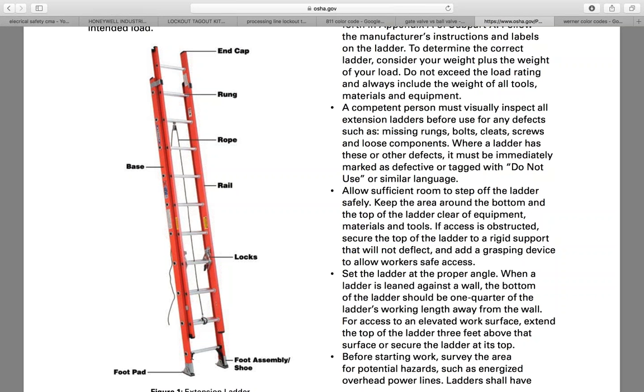Looking at page 14, keep the following precautions in mind. Don't use an aluminum ladder where there are electrical hazards, we just talked about that. Place the ladder on stable ground. Another urban legend: ladders are not required to be tied off at the top or bottom. The only time they're required to be tied off is if they're not on stable ground, there's a risk of them falling, or it becomes a corporate standard within the organizations or environments we're working in.